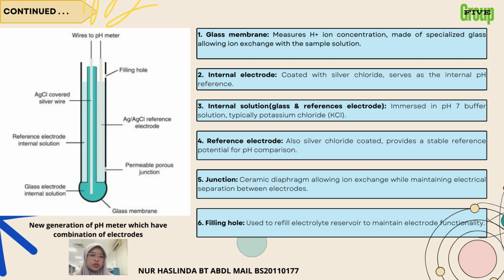This combination electrode integrates all necessary components into a single probe. The glass membrane is the part that measures the H+ ion concentration, made from specialized glass that allows ion exchange with the sample solution. Inside the electrode, there's an internal electrode coated with silver chloride, serving as the internal reference. The internal solution within the electrode is typically a pH 7 buffer solution of potassium chloride, KCl.